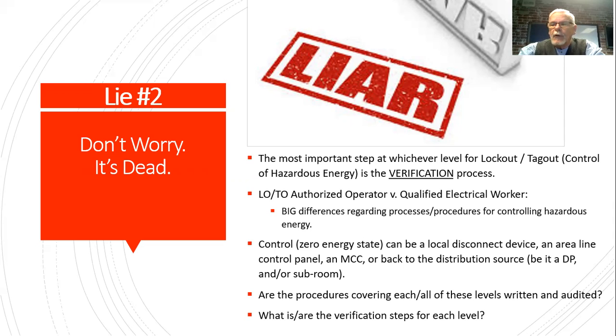Those folks will go to the electrical supply. They will open the disconnect, or they'll throw it to the off position, or they'll turn the rotary switch to the off position, or whatever the switch mechanism is for the machine. They'll apply their lockout device, and then their verification is they will try to start the machine. They will try to start the process. If the process does not start, then they have a successful lockout. They have verified it.